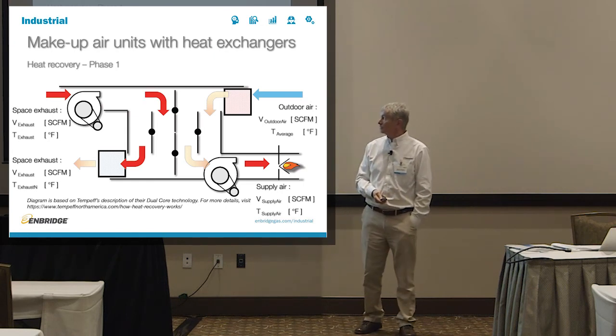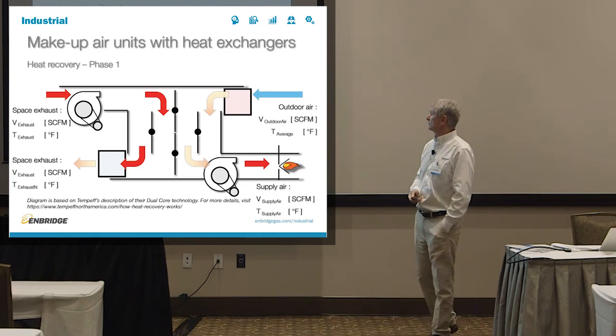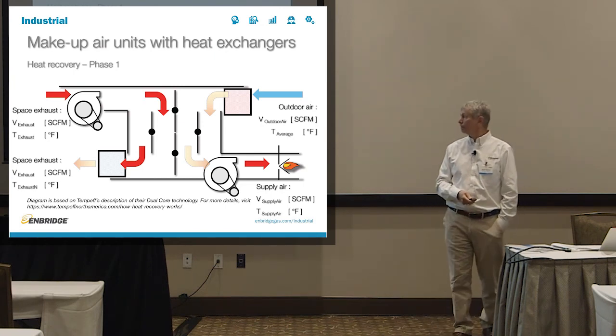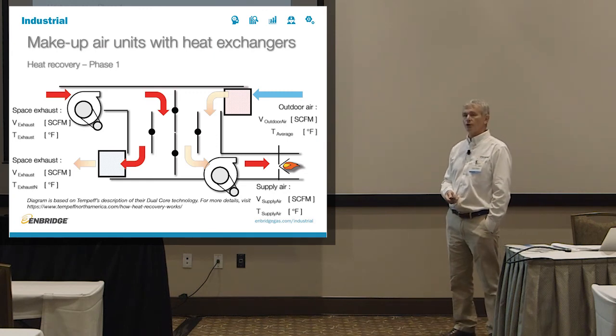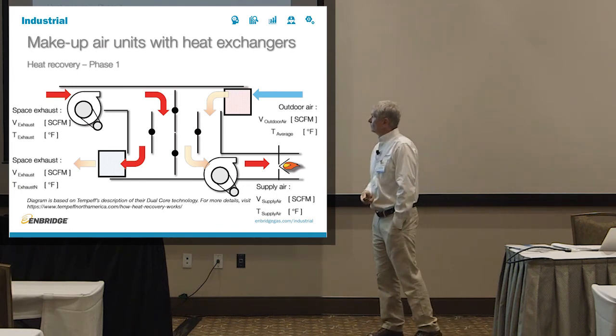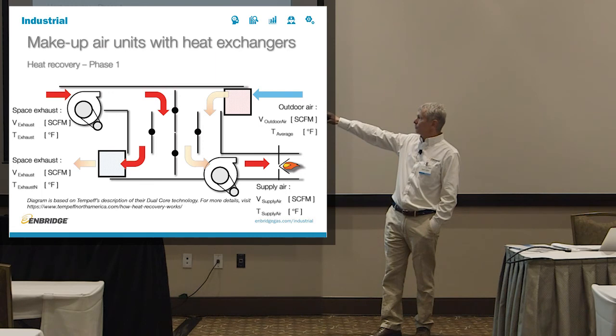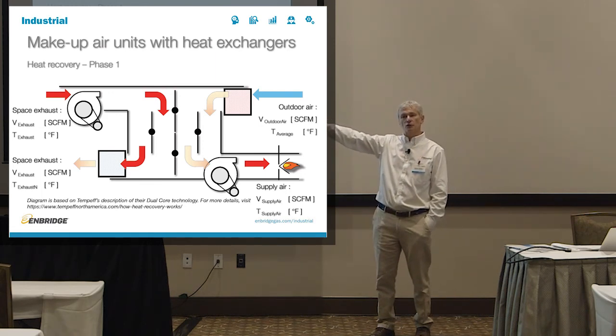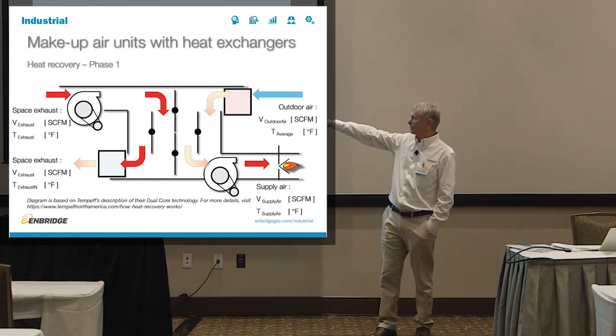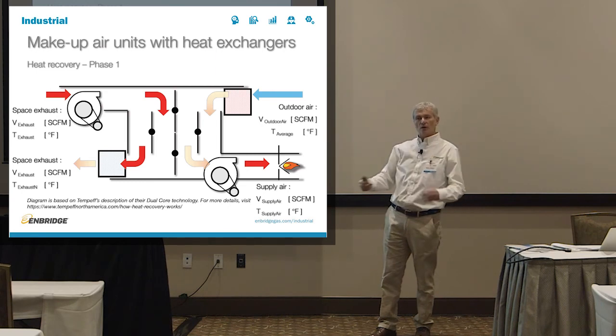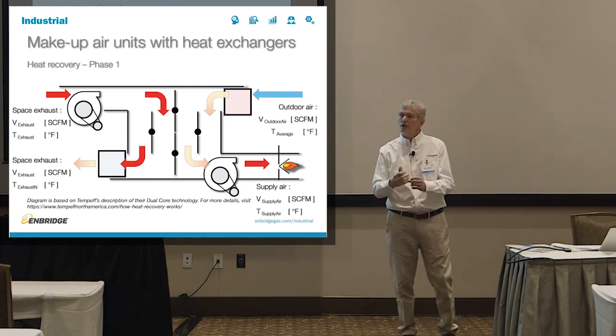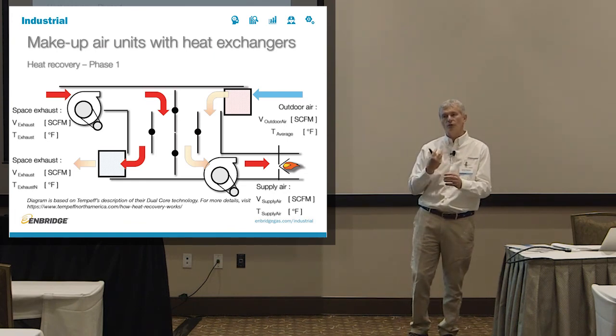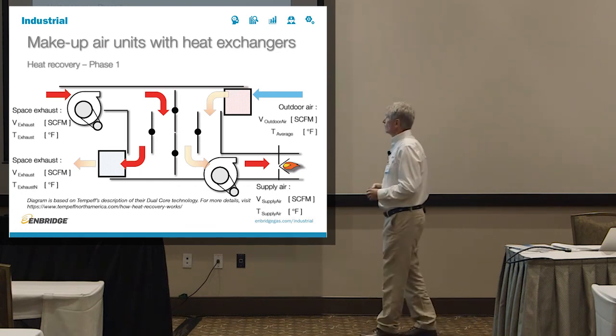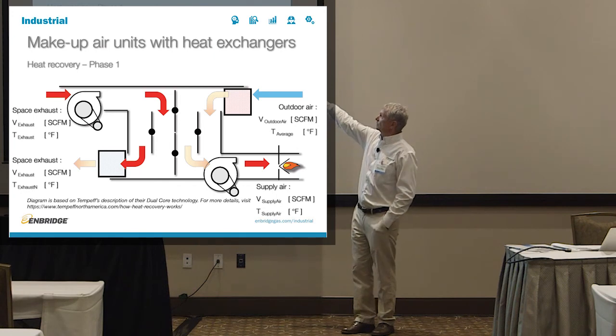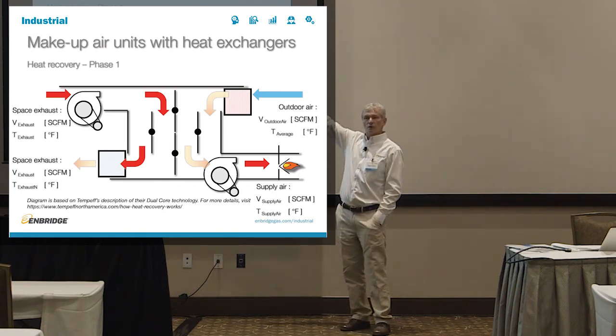They will have a space exhaust fan on one side of the unit, and they will have a supply air fan on the other side of the unit. They will put something called cores on two other entrances. In the first case, the space exhaust stream will go through one of the cores before it exits the unit. So it will preheat the core on your left-hand side with the space exhaust. It's sort of like a ceramic core, and it will absorb the heat out of the exhaust stream, and the exhaust stream coming out of the facility will be colder than what your facility is at now. In the meantime, the core that was previously preheated takes outdoor air that goes through the other ceramic core, preheats that stream of air, and it gets to be the supply air.